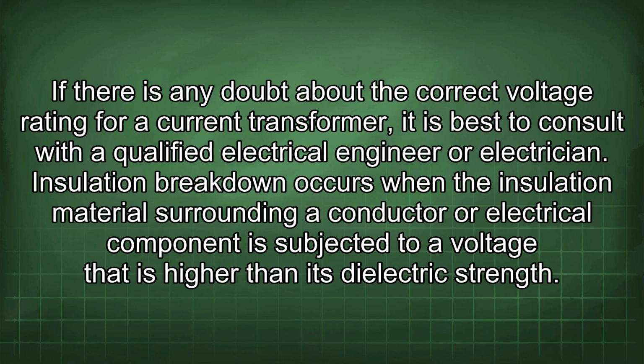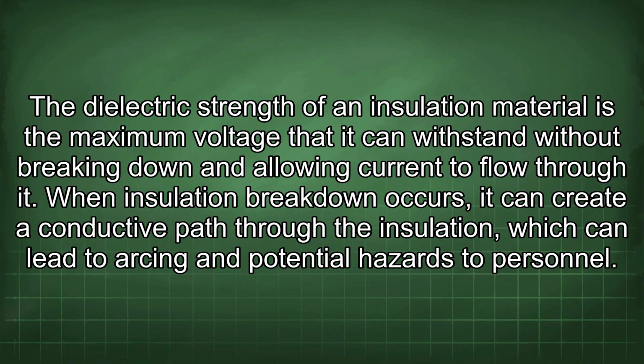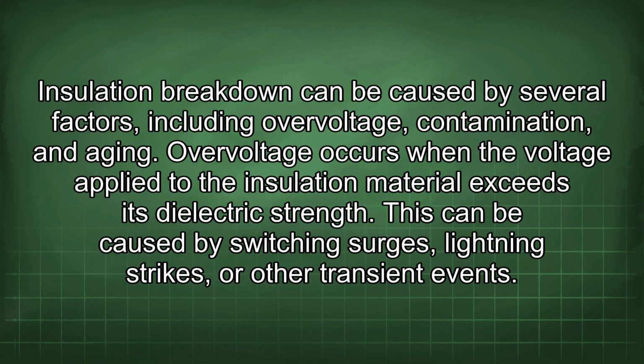Insulation breakdown occurs when the insulation material surrounding a conductor or electrical component is subjected to a voltage that is higher than its dielectric strength. The dielectric strength of an insulation material is the maximum voltage that it can withstand without breaking down and allowing current to flow through it. When insulation breakdown occurs, it can create a conductive path through the insulation, which can lead to arcing and potential hazards to personnel. Insulation breakdown can be caused by several factors, including overvoltage, contamination, and aging.